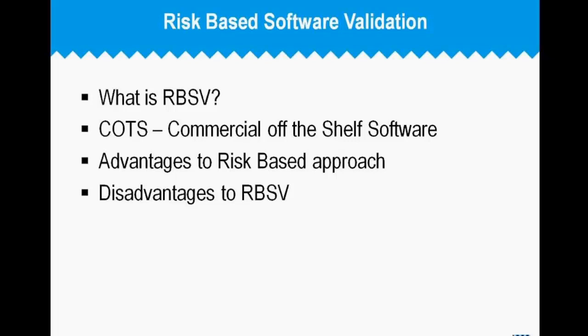Yeah, it definitely is, and I think that's something we wanted to talk about today: the software development environment that you're using and the way it treats the records, quote unquote, that you use for documenting your requirements, documenting your design, documenting your test cases, architecture, all of that is oftentimes done by using commercial software packages. And in this profession, in this industry, we're expected to take a look at how we're using these tools and these software packages for our medical software and evaluate the risk and the applicability that we talked about earlier for validation. And I have good news.